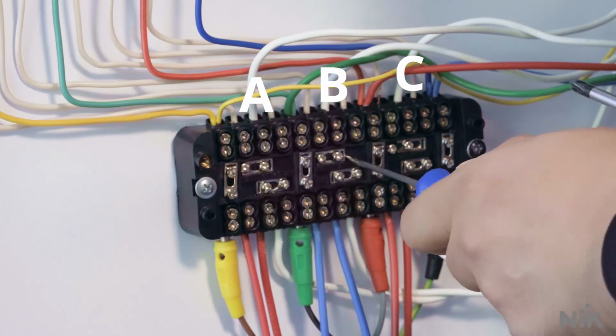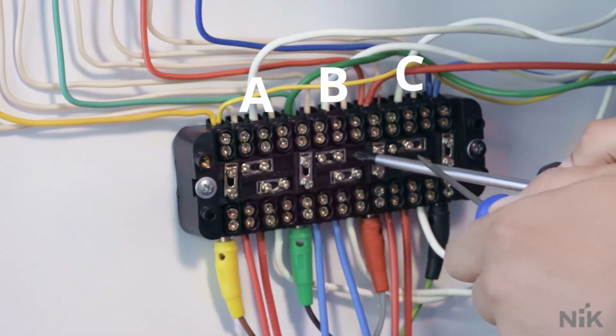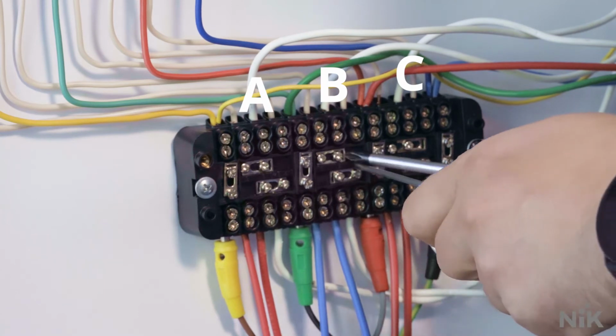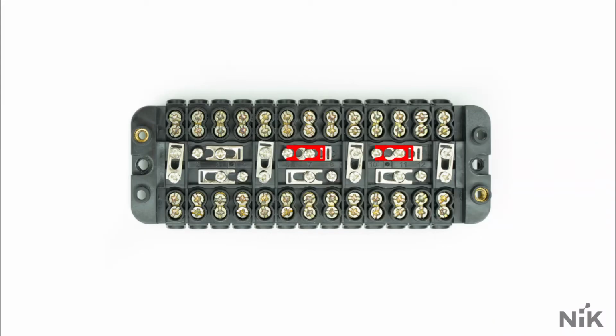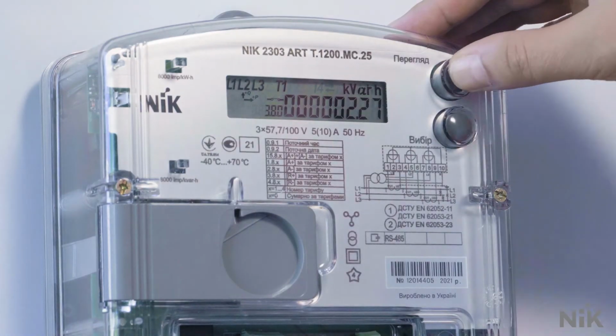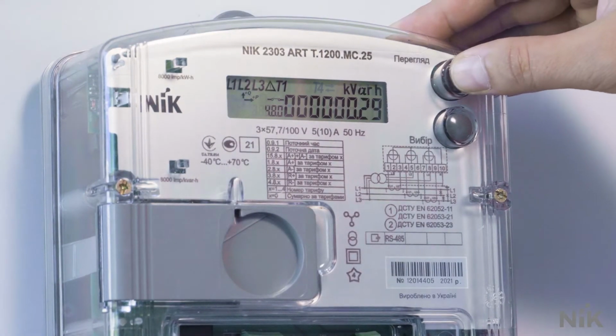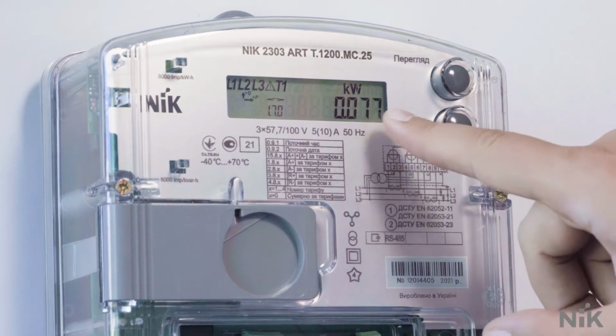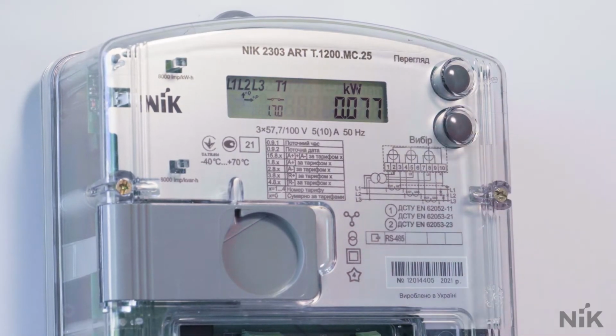Firstly, we unscrew the bolt which holds the jumper for phase B. Secondly, we push the jumper to its maximal left position. Thirdly, we tighten the bolt. Now let's look what do we have. The LED stopped blinking. Let's look at the load. It is practically equals to 0.